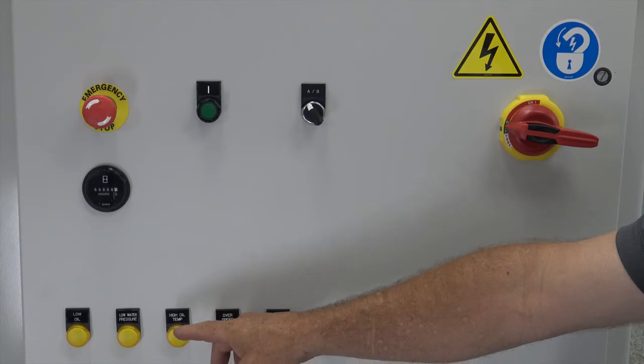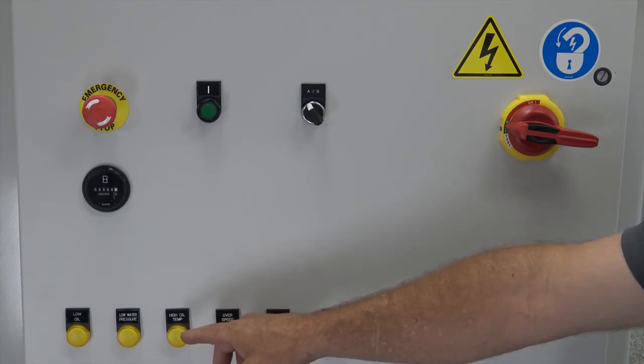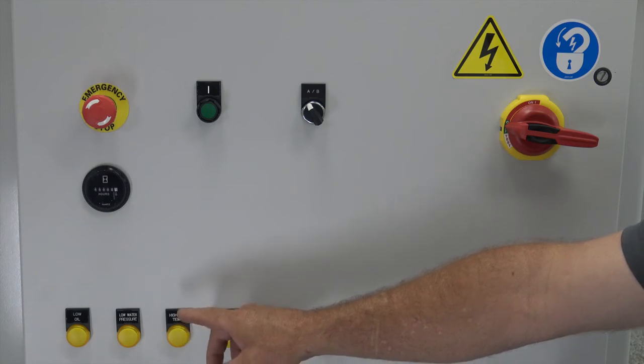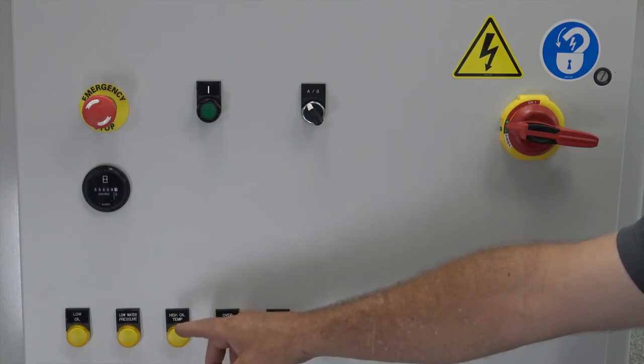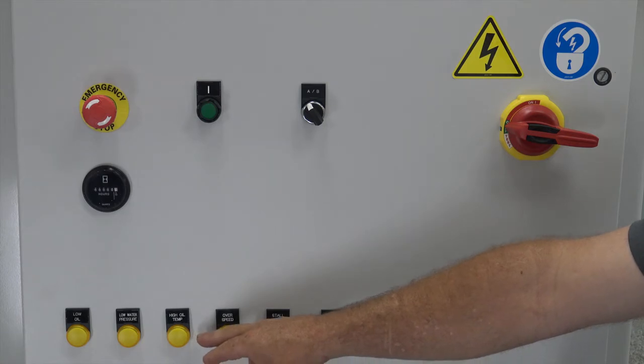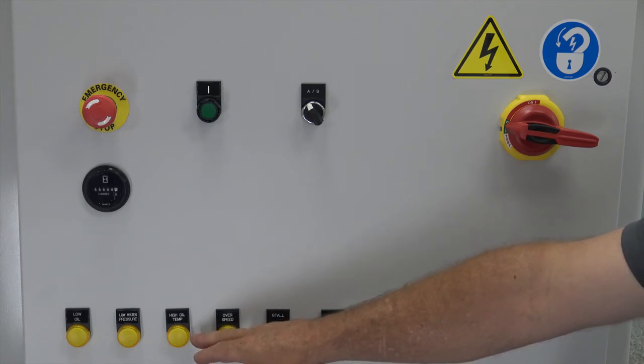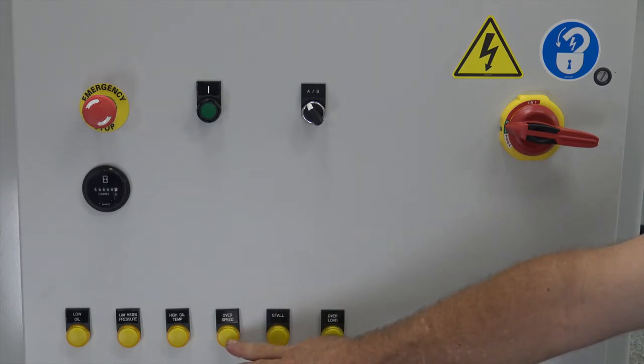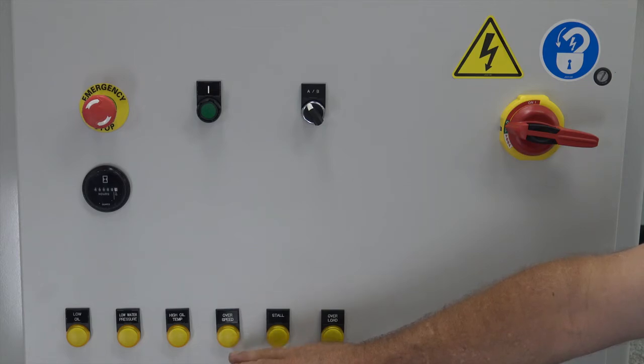Low water pressure is your boosted water pressure. If it comes on telling you that the boosted water pressure is too low, you want to make booster pump adjustments and then restart your unit. High oil temp, the hydraulic fluid inside your reservoir is too high. You'll want to refer to your manual on things that you would adjust or look for on temperature. Overspeed simply means your intensifier is cycling too fast from left to right. Briefly, it could be an orifice, water leaks, things like that, but if the unit is traveling too fast, it'll shut down on overspeed. This helps protect the unit from cavitation.